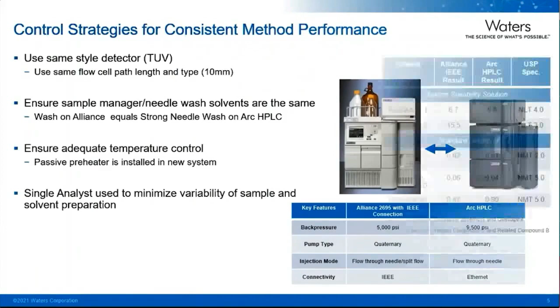Here are the system suitability results for the analysis performed on both the ARC HPLC and the Alliance IEEE. Shown on the left is a system suitability solution. For both the system suitability solution and the standard solution, both systems met all of the USP specifications and were well within the requirements. This included resolution of quetiapine and quetiapine desoxy, resolution 1, as well as the resolution between related compound G and related compound B, which are peaks 1 and 2. Furthermore, the tailing factor, retention time RSDs, and area percent RSDs were well below the limit of not more than 5%.